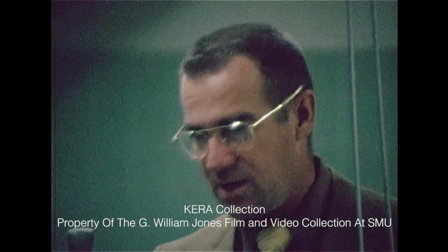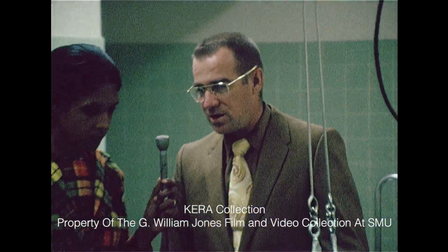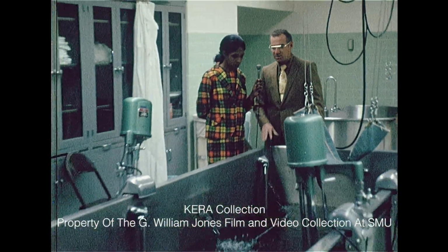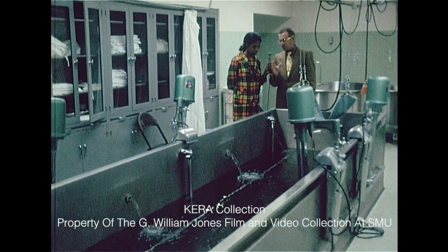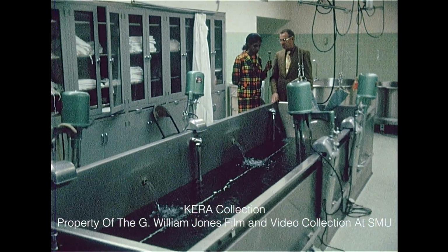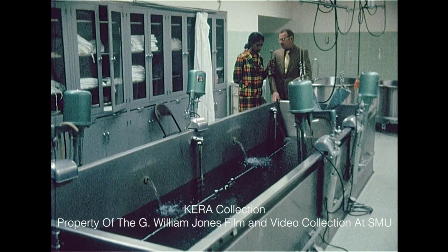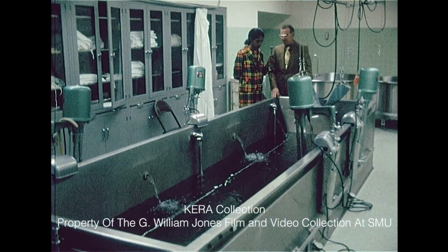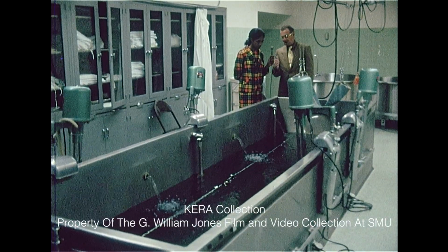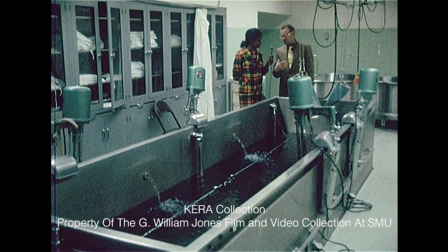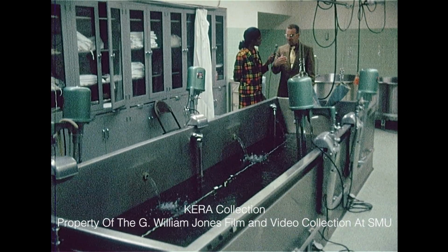These motors are 110 volt. The circuits that they run through, and the circuitry coming to and from them, are grounded in such a manner and checked at intervals to assure that the patient is in a safe and proper environment at all times. Also, you must remember that the piping to and from this unit is all solid copper, and it also provides somewhat of a ground.